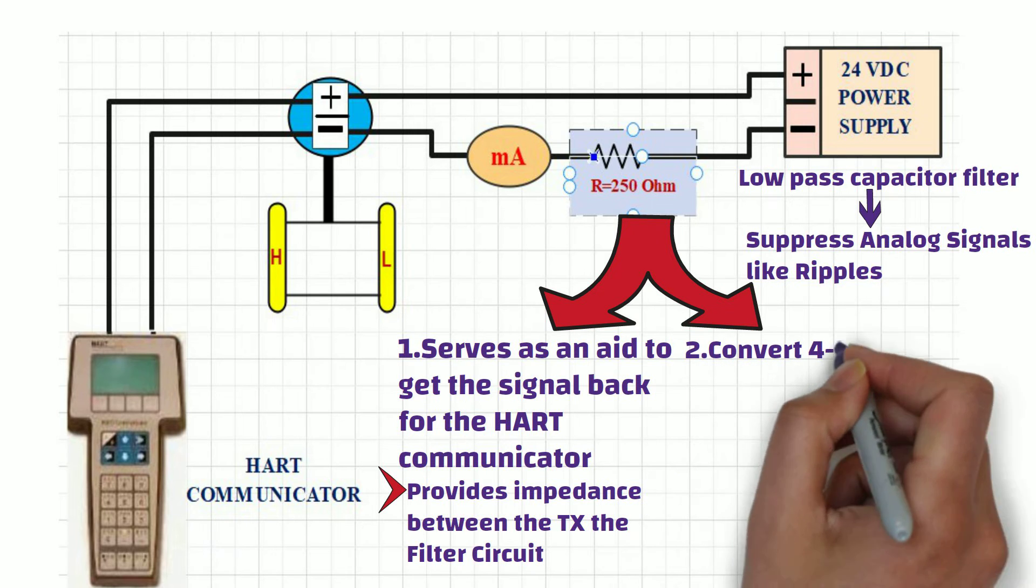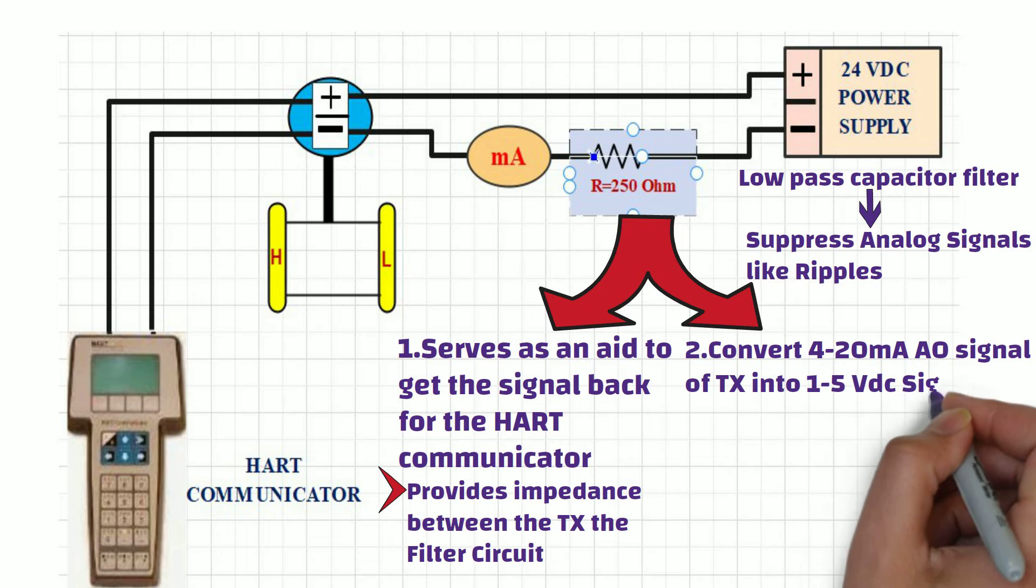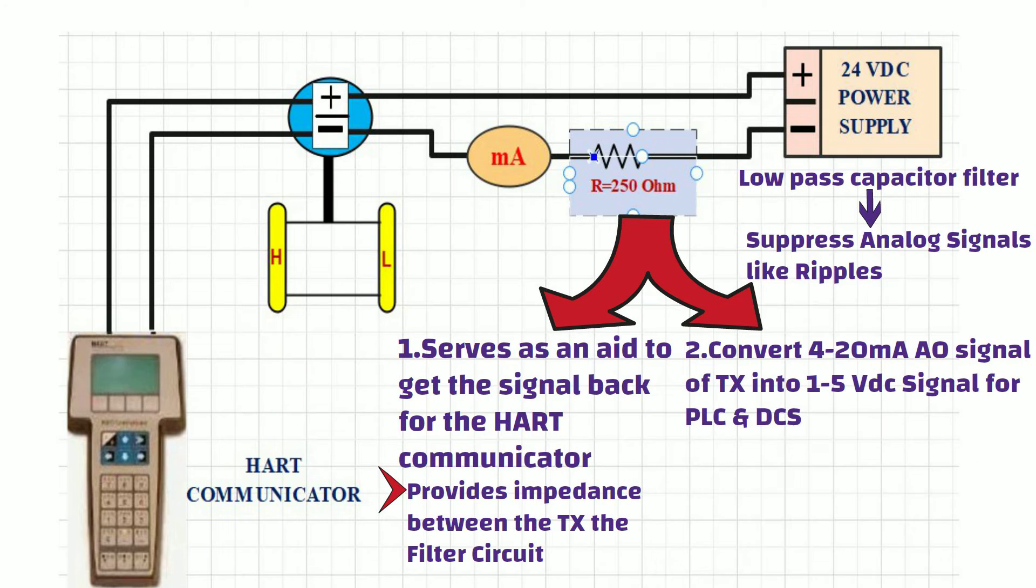Secondly, 250 ohm resistor is used to convert 4 to 20 mA analog output signal of transmitter into 1 to 5 volt DC signal, which is required for DCS and PLC.